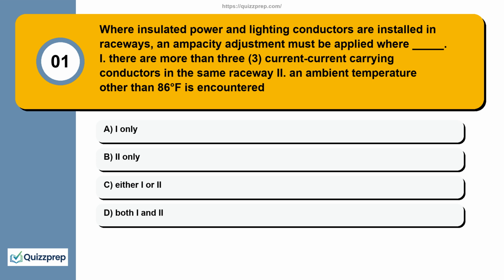Question 1. Where insulated power and lighting conductors are installed in raceways, an ampacity adjustment must be applied where: 1. There are more than 3 current carrying conductors in the same raceway. 2. An ambient temperature other than 86 degrees Fahrenheit is encountered. I only, 2 only, either 1 or 2, both 1 and 2.